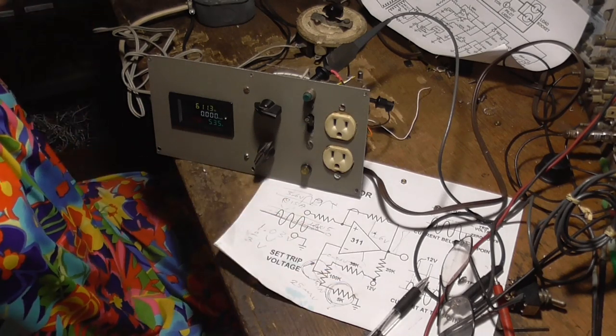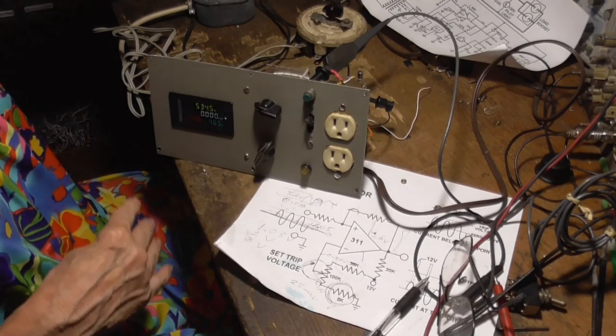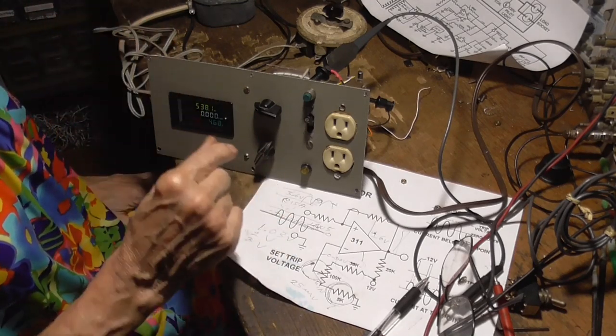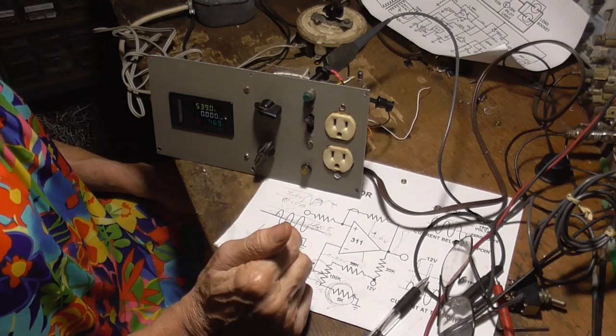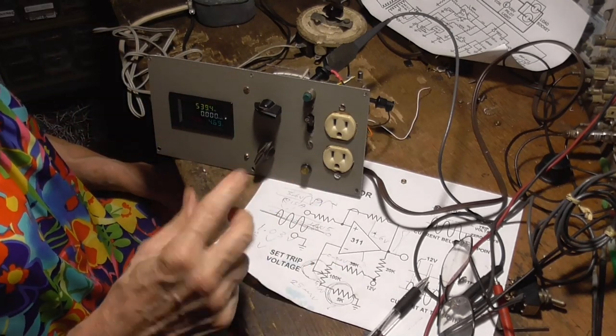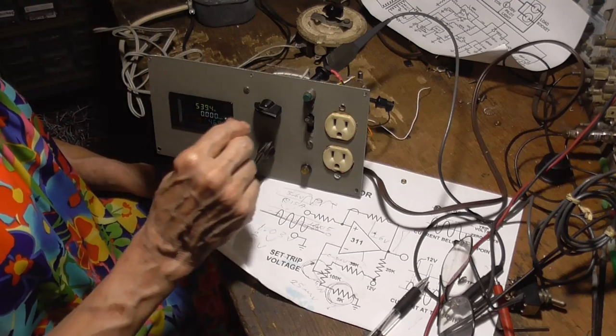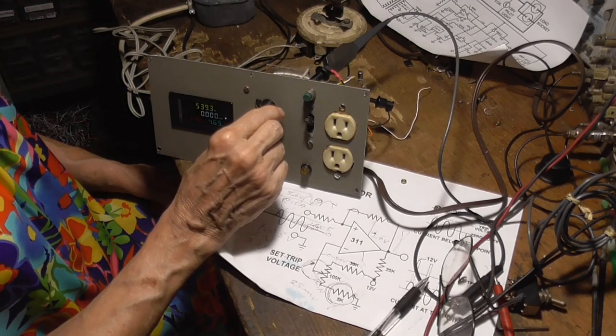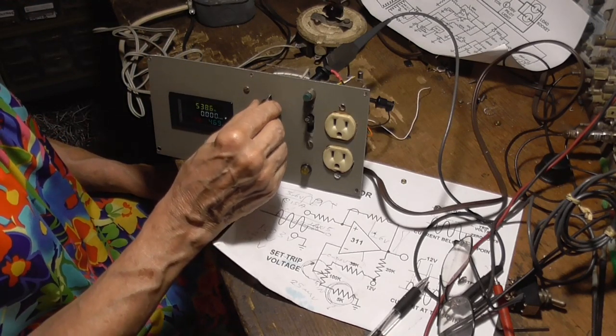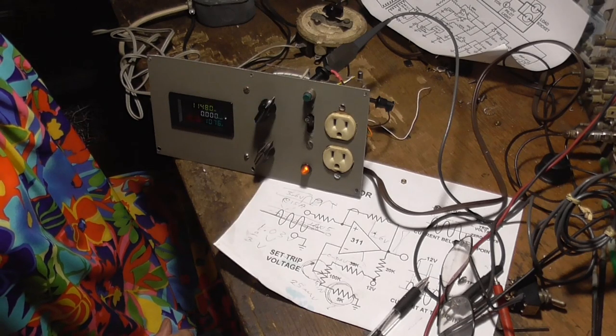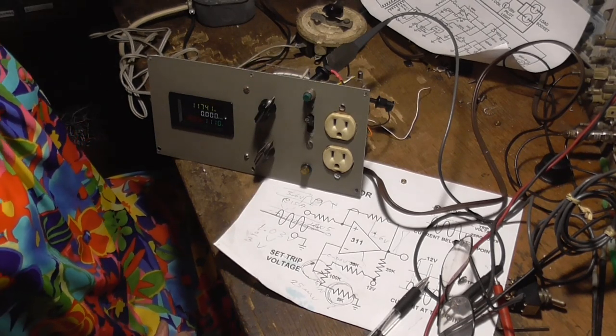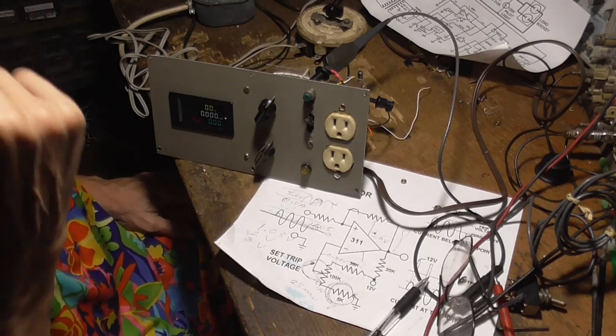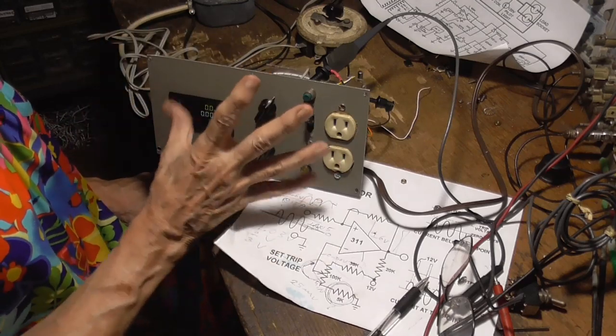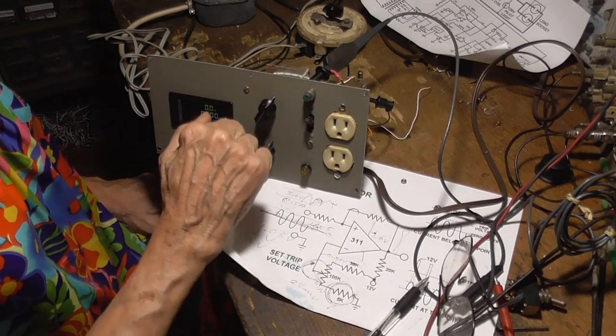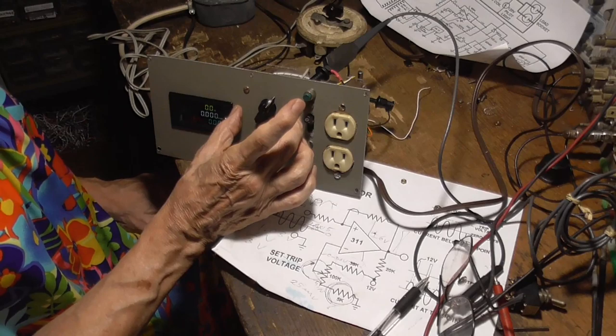Now I'm going to set it up to 2 volts, and that should be 10 amps. That's the limits of my variac here. I don't want to go past 10 amps on the variac, it's a 10 amp variac, and I don't want to risk burning up the brush on it. Okay, I'm going to set it to 2 volts. About 11 amps, okay, we'll leave it right there. So it triggers at 11 amps when set there. It's okay, when we calibrate this, we'll go ahead and set it to read correctly.